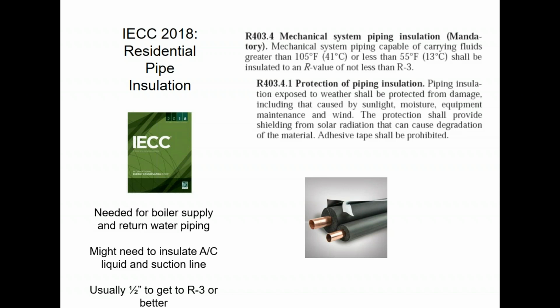Terry says for boiler insulation. It is irrespective of the location of the piping. Inside the envelope or outside the envelope, I'm going to have to insulate the piping. All piping if the temperature is above 105 or below 55. If it happens to be outdoors, then in that case, I'm going to have insulation that's UV resistant and so forth. It actually even says it in the code here.